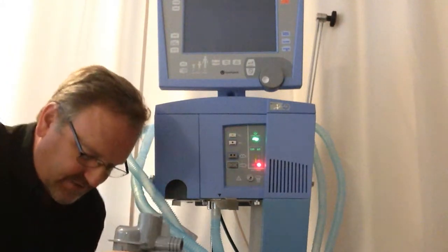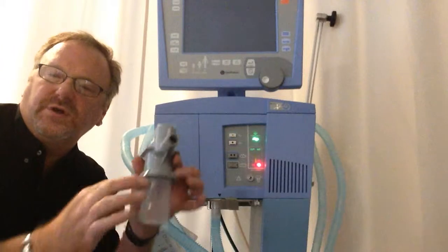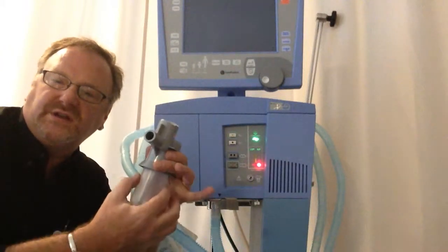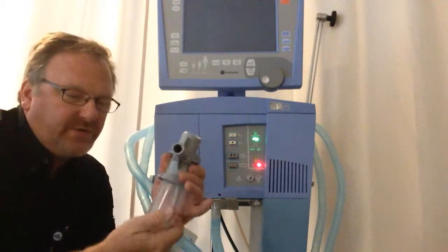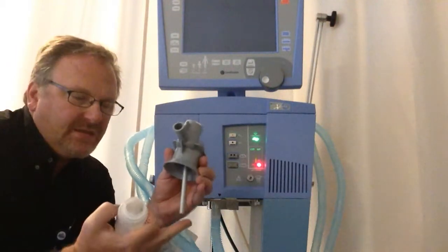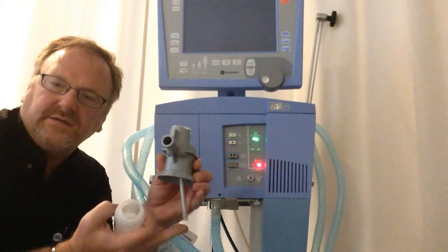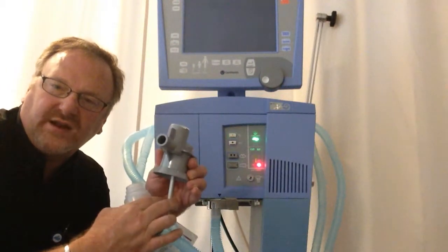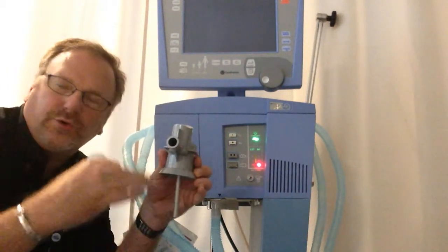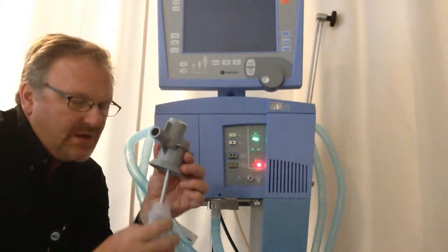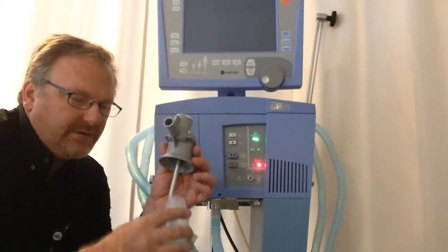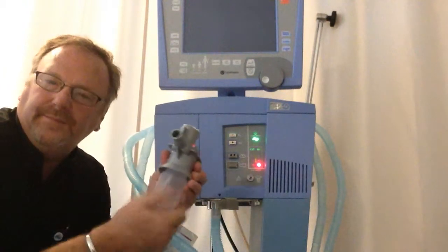What this does is, if there's a lot of condensation in the filter, it'll drip down in this bottle. When it starts getting a lot of water, you need to empty it. You empty it by unscrewing it and then dumping it wherever you need to dump it. This is a weighted ball valve, so it cuts off and it should not let any pressure or gas leak out of the system. So you take it off, dump it, and put it right back on.